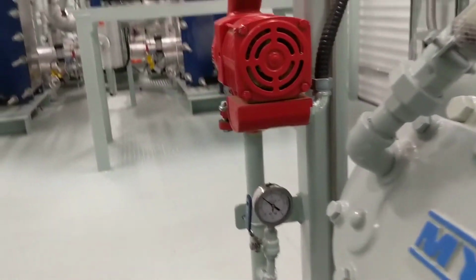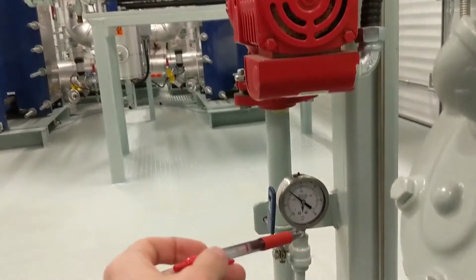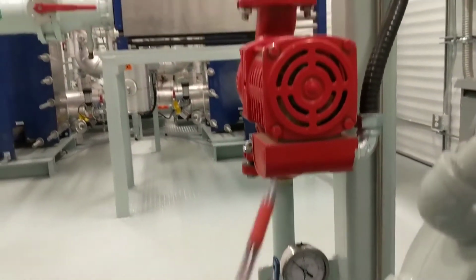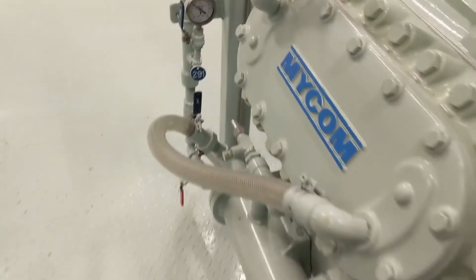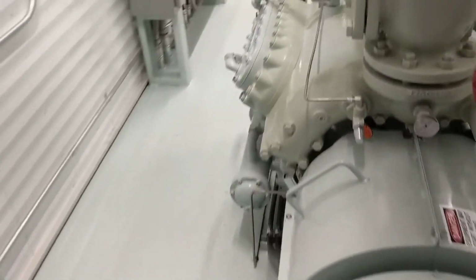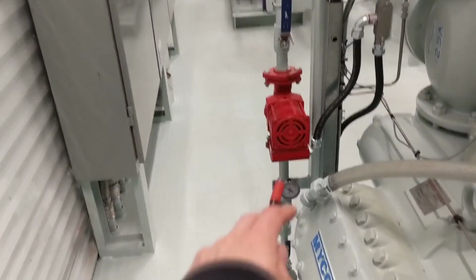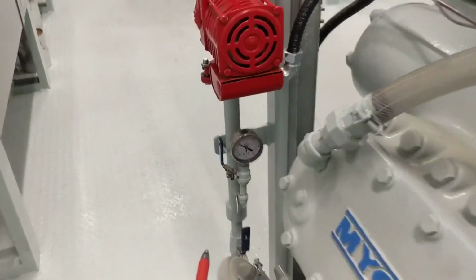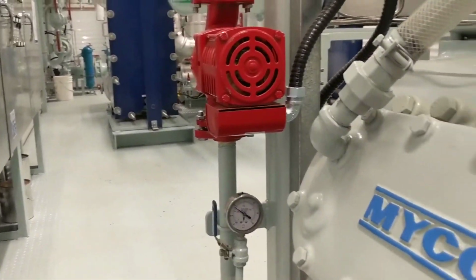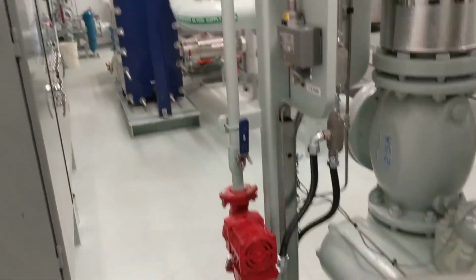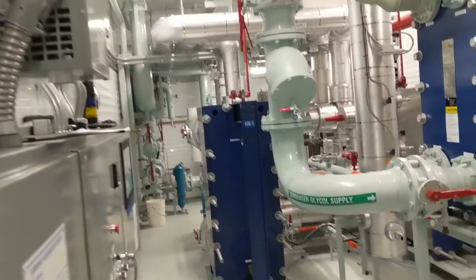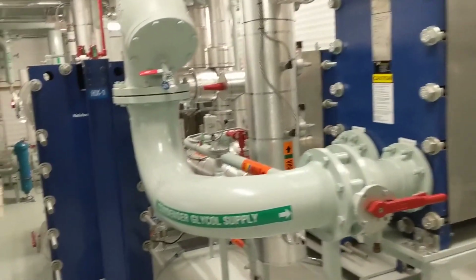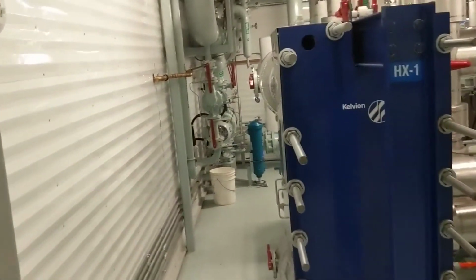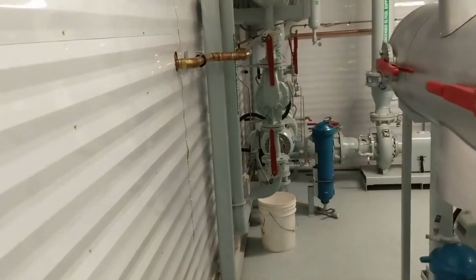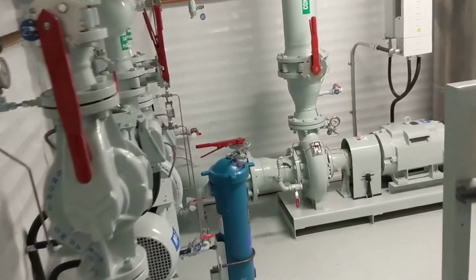Down here, just below your pump, this is the pressure that your glycol pump for your compressor cooling is running at. Over on compressor 1, you'll see the same thing where you've got your circulation pump and then you've got your pressure that it's running at. That should pretty much cover everything for the glycol portion of the refrigeration cycle. And I hope that makes things a little clearer.